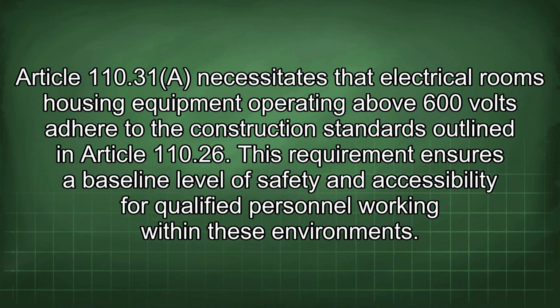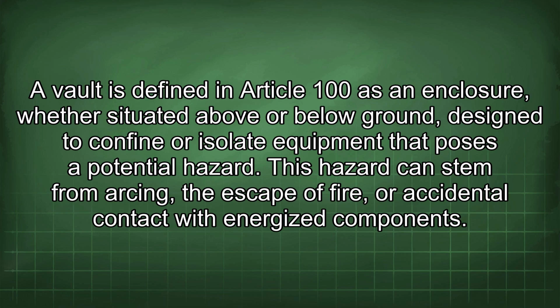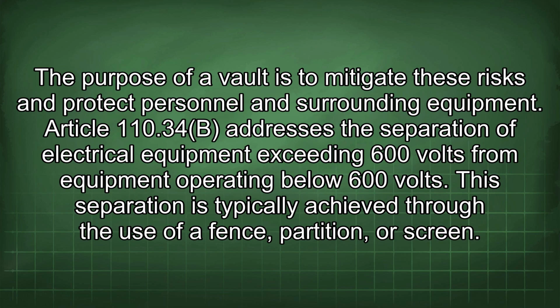Article 110.31 necessitates that electrical rooms housing equipment operating above 600 volts adhere to the construction standards outlined in Article 110.26. This requirement ensures a baseline level of safety and accessibility for qualified personnel working within these environments. A vault is defined in Article 100 as an enclosure, whether situated above or below ground, designed to confine or isolate equipment that poses a potential hazard. This hazard can stem from arcing, the escape of fire, or accidental contact with energized components. The purpose of a vault is to mitigate these risks and protect personnel and surrounding equipment.